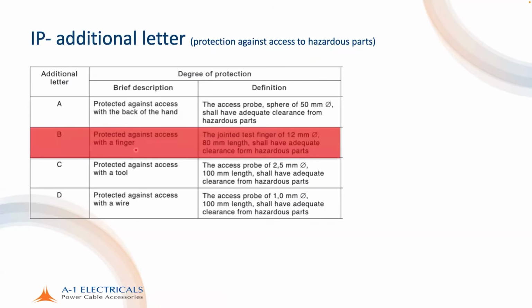The B means that there is protection against access with a finger. The test is done with a simulated finger, 12 mm diameter, 80 mm length, and it shall not be able to access any hazardous part. The D means a probe of 1 millimeter diameter, 100 millimeter length cannot access any hazardous part. That is what it means.